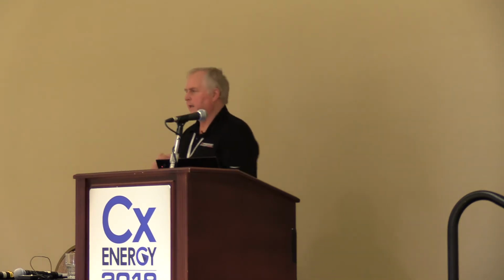So those are mainly, like I said, industrial, but think about retrocommissioning. If you start looking at retrocommissioning pneumatic controls and pneumatic actuators and pneumatic valves and damper controls, and doing these with electric, don't forget to look at the calculation for the cost savings you'll get by not doing it pneumatically. If you're not putting it in your cost, put it in as part of the cost savings and justification for your project.